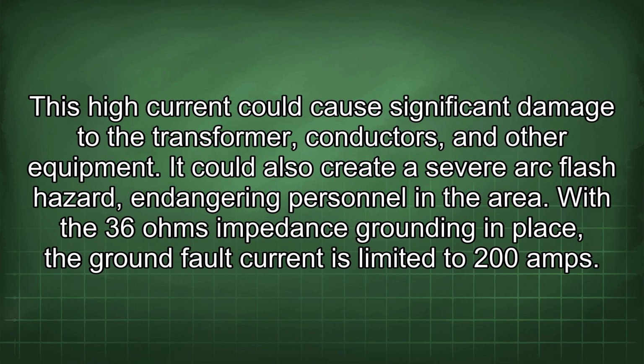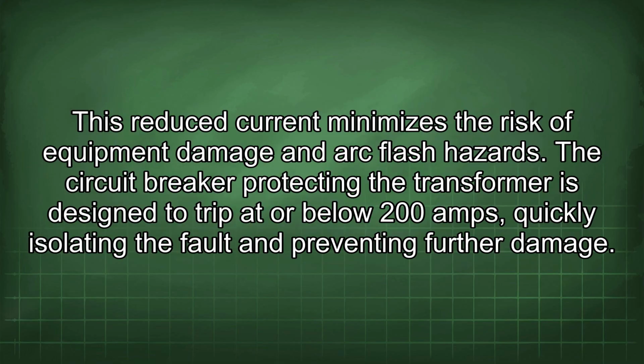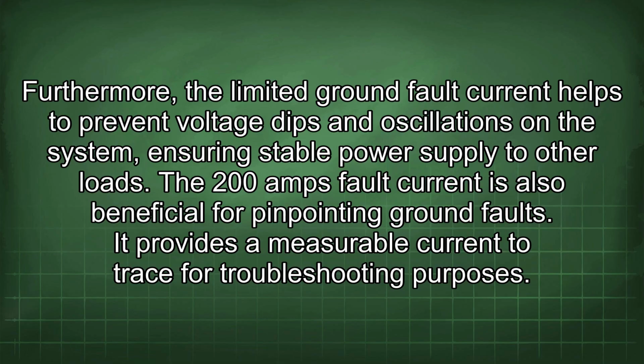With the 36 ohms impedance grounding in place, the ground fault current is limited to 200 amps. This reduced current minimizes the risk of equipment damage and arc flash hazards. The circuit breaker protecting the transformer is designed to trip at or below 200 amps, quickly isolating the fault and preventing further damage. Furthermore, the limited ground fault current helps to prevent voltage dips and oscillations in the system, ensuring stable power supply to other loads.